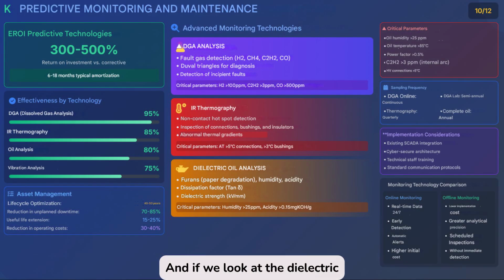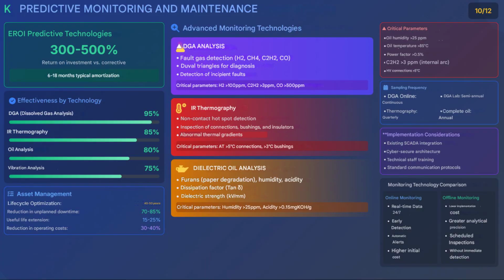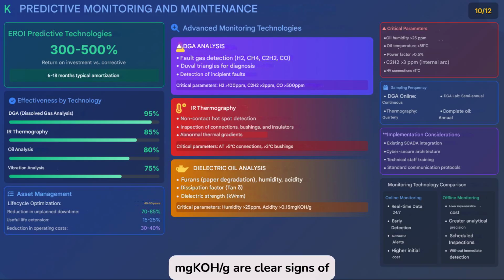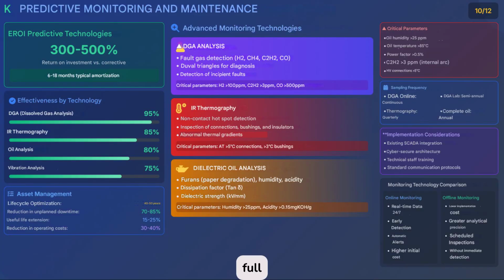And if we look at the dielectric oil analysis, we find even more useful information. Furans indicate degradation of the insulating paper, while humidity, acidity, and dielectric strength alert us to critical conditions. Values such as humidity above 25 ppm or acidity above 0.15 mg KOH/g are clear signs of aging or contamination that, if detected early, can be corrected with relatively simple measures before compromising the plant's full functionality.